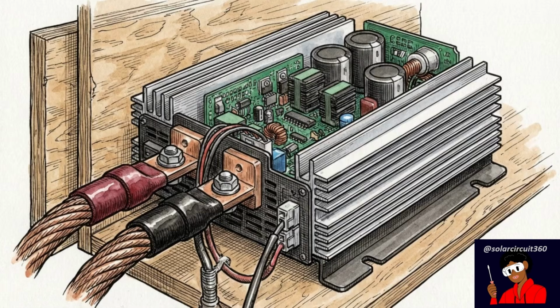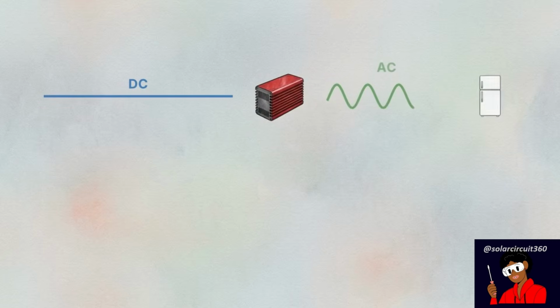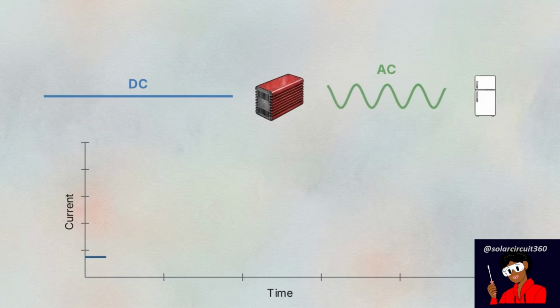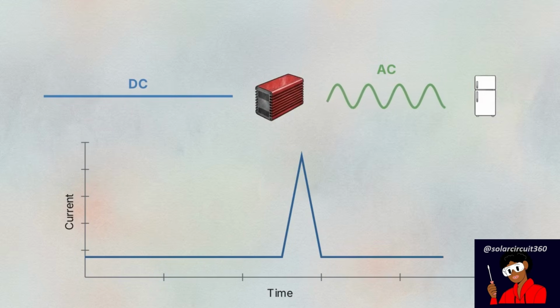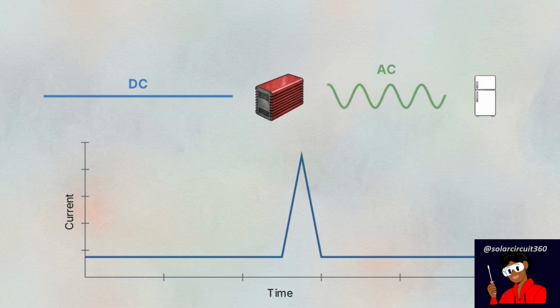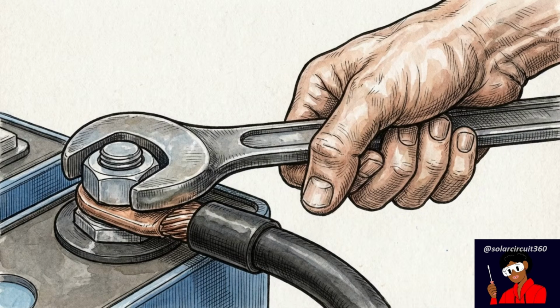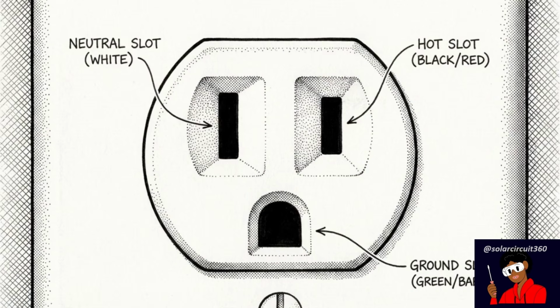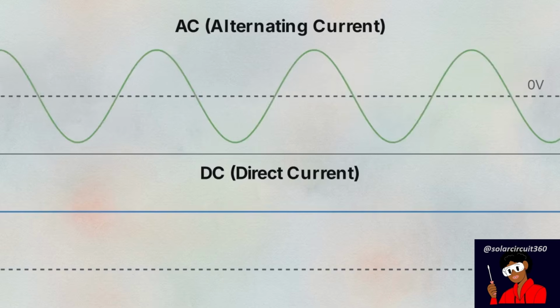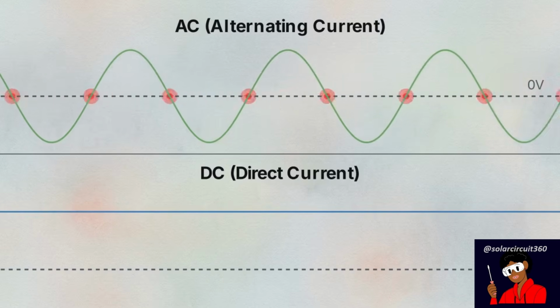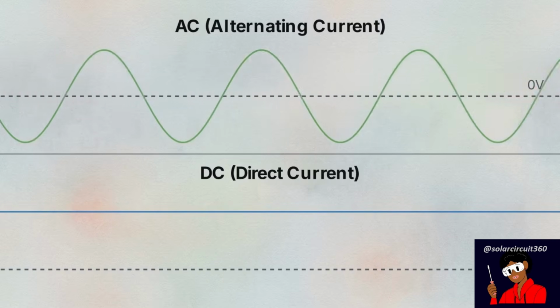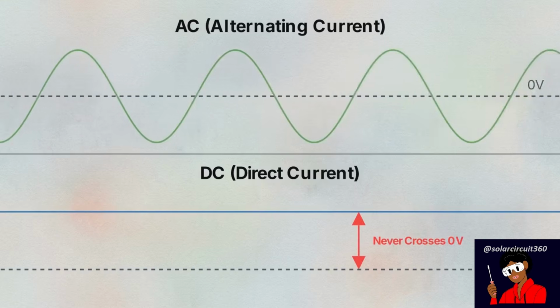That electrical stress is amplified by the inverter. The inverter translates battery power into the usable power your household appliances need, and it draws a massive, instantaneous surge of current every time it starts up. The power flowing from your battery to the inverter is direct current, or DC. This behaves very differently from the alternating current, or AC, found in a standard wall outlet. AC power pulses, dropping to 0 volts dozens of times a second. DC power does not naturally cross zero.